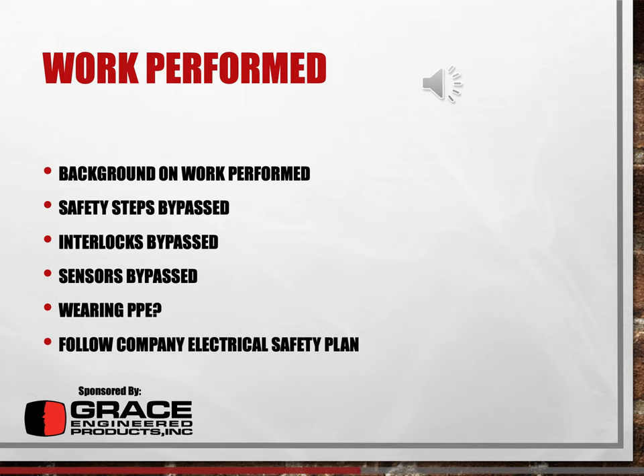Was the person wearing PPE? Was it appropriate PPE? What does the arc flash label say? What kind of PPE were they supposed to wear? And were any sensors bypassed? Was there a bad sensor where jumper wires were used? Those things are pretty critical in determining what happened. And if it's in a control panel, I can almost guarantee you the third-party experts are going to be tracing that control panel, every connection inside there, to see if anything was jumpered.